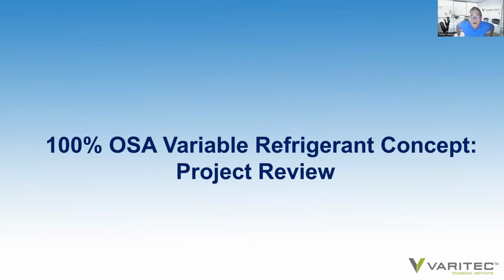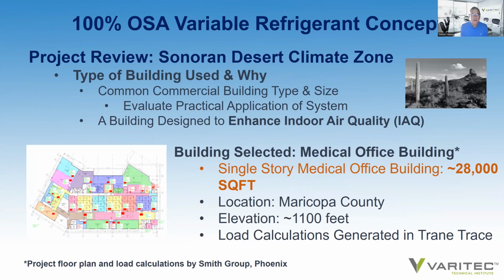So, 100% outside air, variable refrigerant concept. Let's look at an application. How do we apply this concept to an actual project design? Well, I was working with the Smith Group team on a project, and I thought it'd be good to evaluate a 100% outside air variable refrigerant system for a more common building type, a building that has less or medium square footage, buildings that we see more often than not as opposed to large institutional applications.